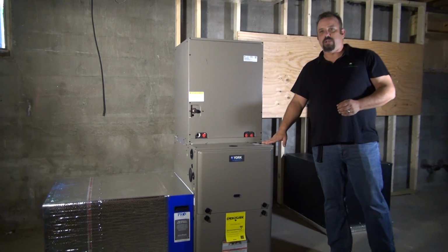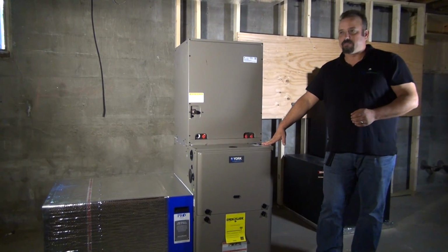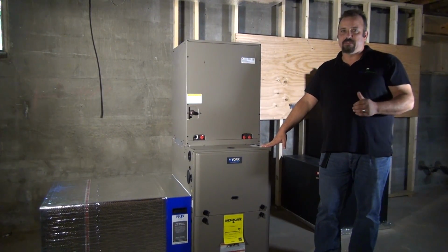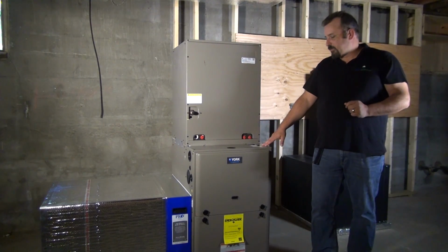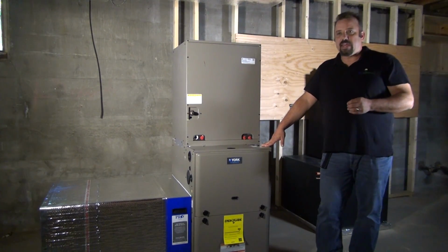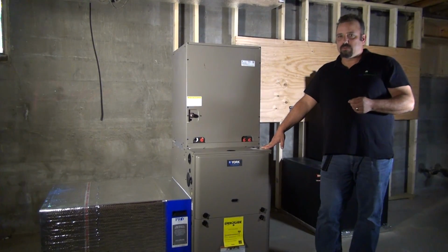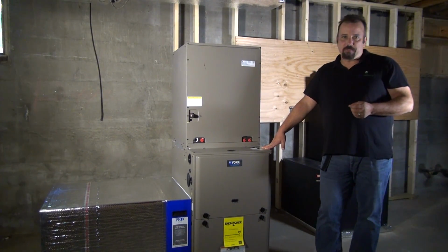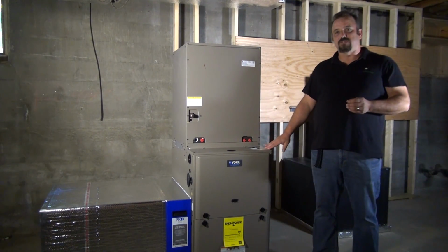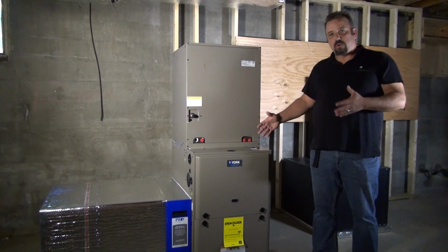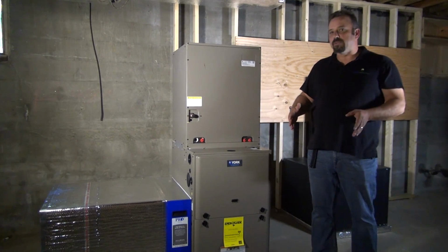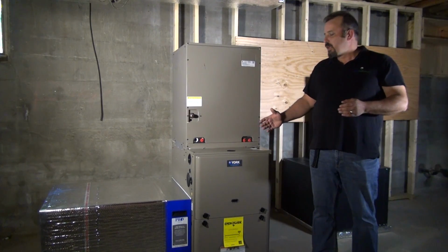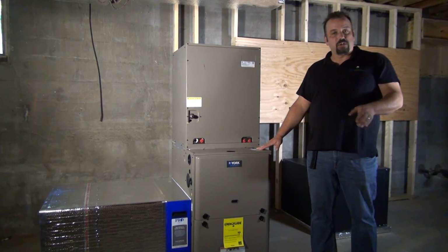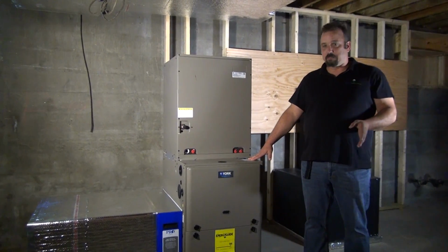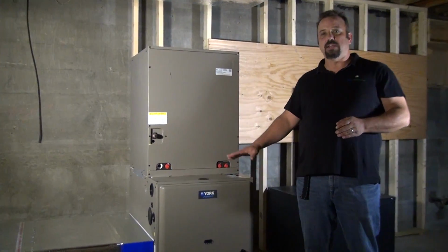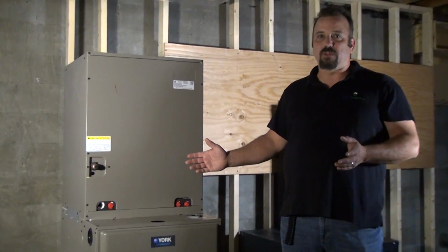Now, the gas will not be running during that portion of time when the geothermal is on. The reason why there's a gas furnace here in place of just a straight geothermal heat pump is the gas furnace acts as a forgiving source to power outage. In a typical geothermal heat pump, you'll have backup KW heating, which is an electric strip heating element. So basically, if there is an emergency purpose, so to speak, or extremely cold temperatures, and the geothermal for some reason does not keep up with the load in the house at that particular point in time, the gas furnace can now come on and work in conjunction with the geothermal. And that's done strictly through your thermostat.